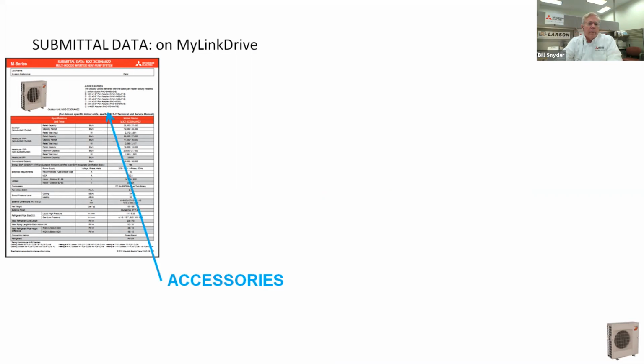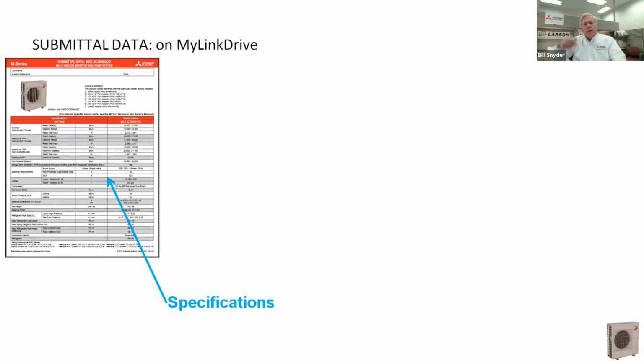Up at the top of the page here are accessories. And down here are all the specifications. The specifications are the wiring size and the amp draw, so that you can determine what size service breaker you need. It gives you your piping diameters. It gives you your piping lengths, minimum and maximum lengths, the height difference, and how many feet of separation you can have. All that is typically on page 1.